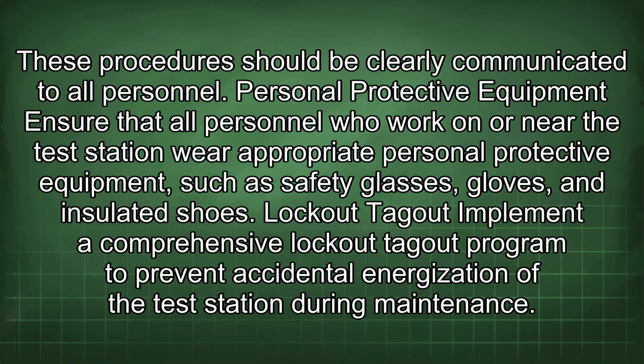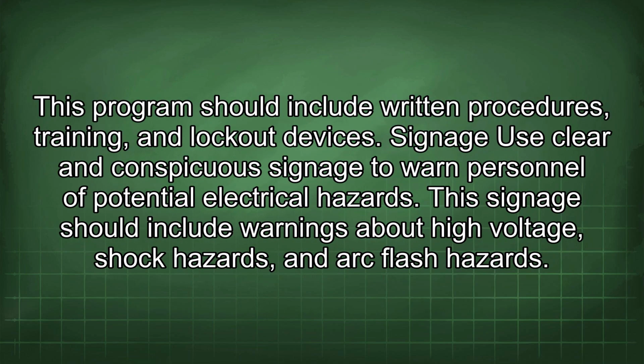Lockout tagout: implement a comprehensive lockout tagout program to prevent accidental energization of the test station during maintenance. This program should include written procedures, training, and lockout devices. Signage: use clear and conspicuous signage to warn personnel of potential electrical hazards. This signage should include warnings about high voltage, shock hazards, and arc flash hazards.